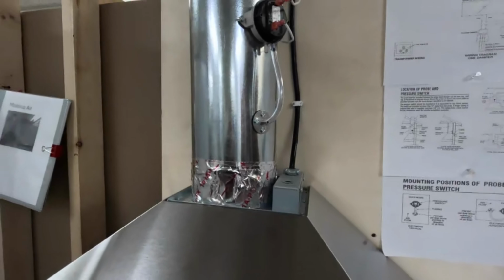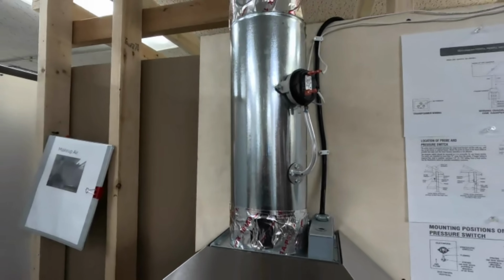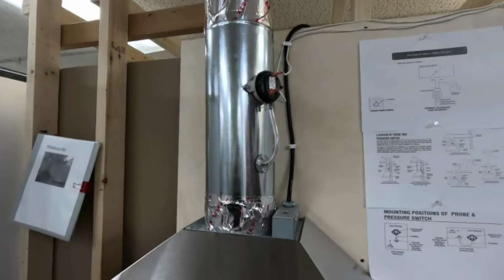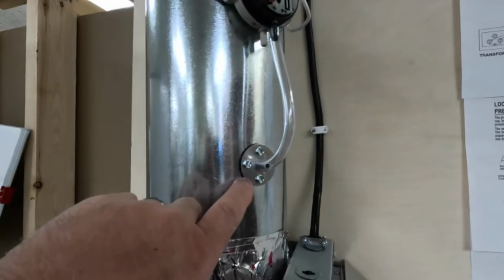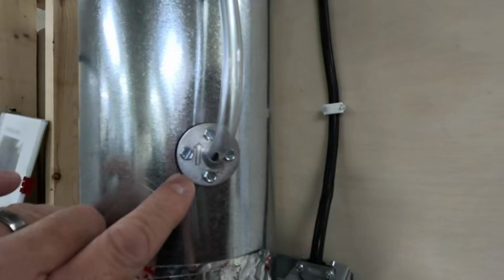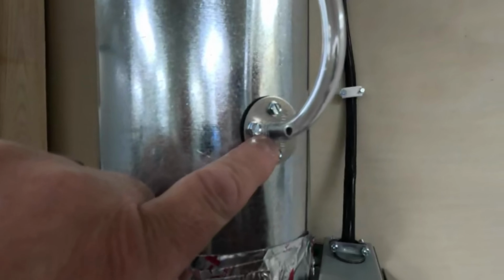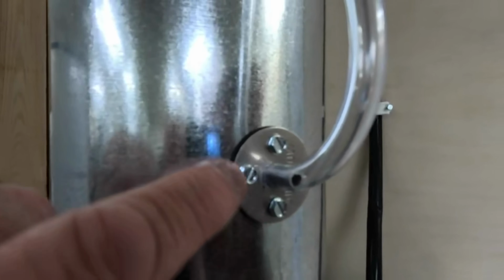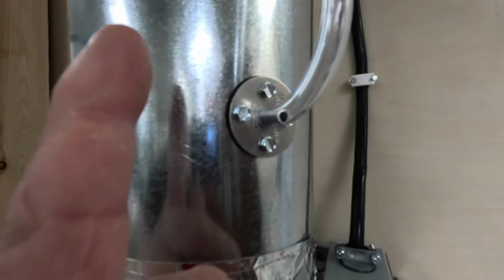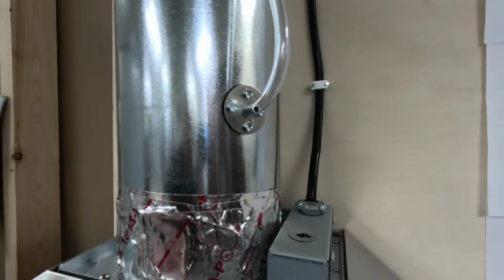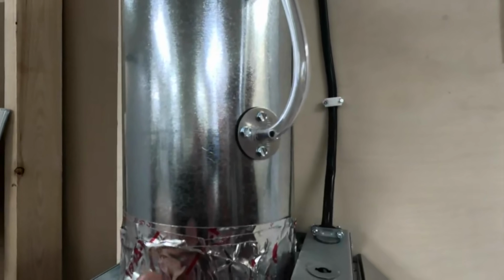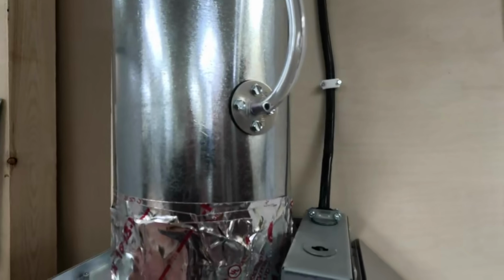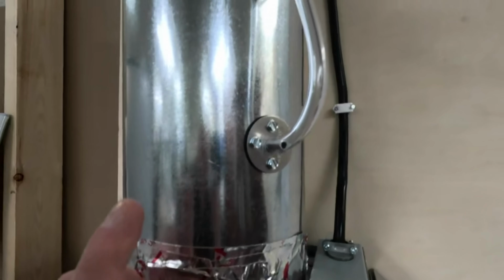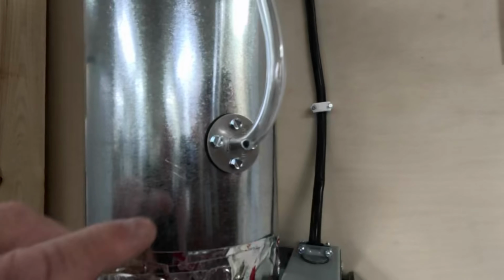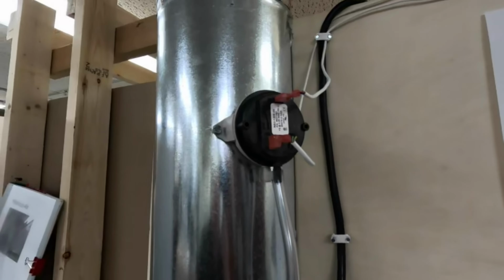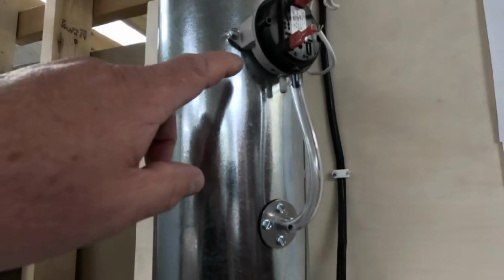As you can see how I have this wired, this is a vertical duct application. I went ahead and drilled 4 holes and inserted my probe. It might be hard to see, but there's an arrow pointing up on this probe. That arrow represents the way the air flows up the ductwork, so it must be pointing basically in the up position. If you take a look, the pressure switch must be orientated just like this.